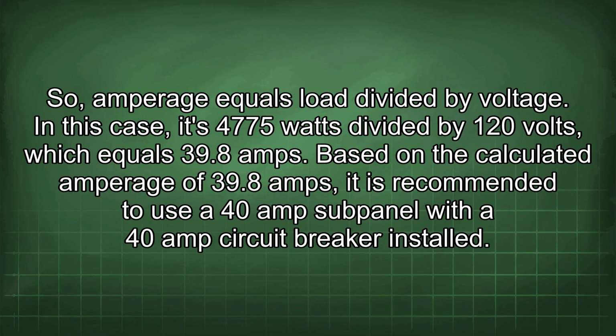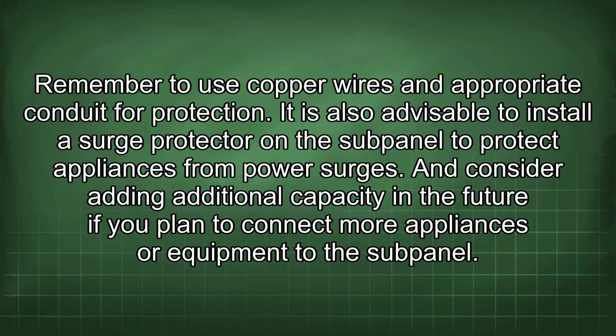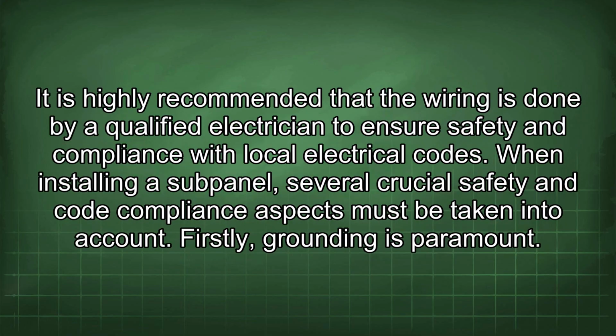Based on the calculated amperage of 39.8 amps, it is recommended to use a 40 amp subpanel with a 40 amp circuit breaker installed. Remember to use copper wires and appropriate conduit for protection. It is also advisable to install a surge protector on the subpanel to protect appliances from power surges. And consider adding additional capacity in the future if you plan to connect more appliances or equipment to the subpanel. It is highly recommended that the wiring is done by a qualified electrician to ensure safety and compliance with local electrical codes. When installing a subpanel, several crucial safety and code compliance aspects must be taken into account.